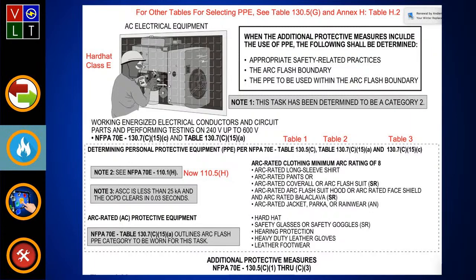Now, you may say, well, we're a little bicycle shop. We don't have engineering, qualified electricians to actually do this in that manner. Then you could go over to Annex H, look at your table H2, and you could select category 1 and 2 for everyday work. And then when you get into the heavier type work, you would use category 3 and a moon suit. And you could just go by that table. So that is 3 methods, right? Yeah. You have the table 130.5G. Then you come down to the 3 tables that we went over, table 1, 2, and 3. And then you have the table H2, that's 3.